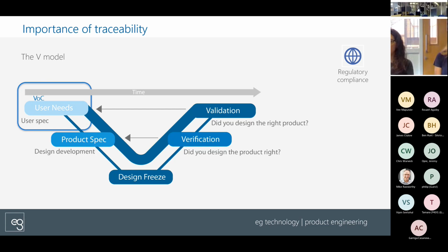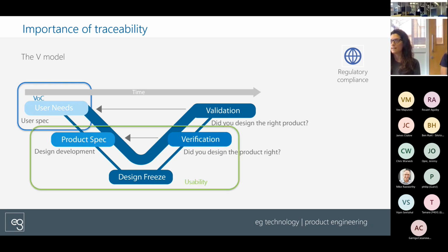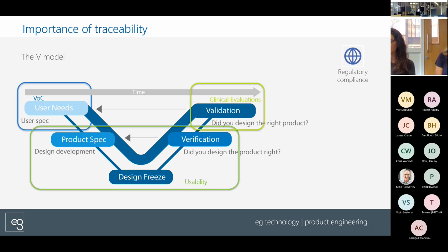And where the elements that we're talking about today sit on this diagram: voice of the customer, as we said, is at the beginning, and doing that primary user research helps you then define your user needs. For usability testing, you start from that user research, distill out the product requirements, and design your product, including the user interface. So this V model applies to your whole product development. Usability is a part of that, but it follows the same model, in that once you design your user interface, you're then verifying that it meets your user interface specification, and ultimately validating your user interface, and then moving on to clinical evaluations, which, as we've said, is your ultimate validation step.